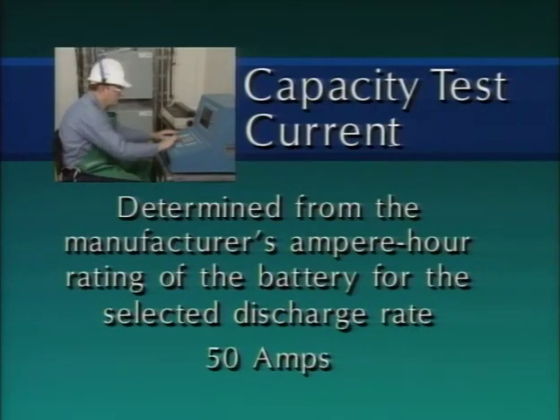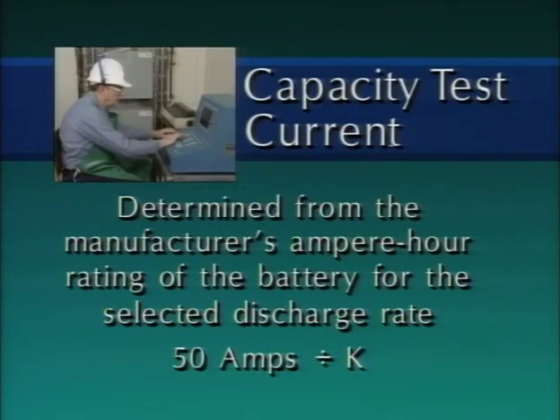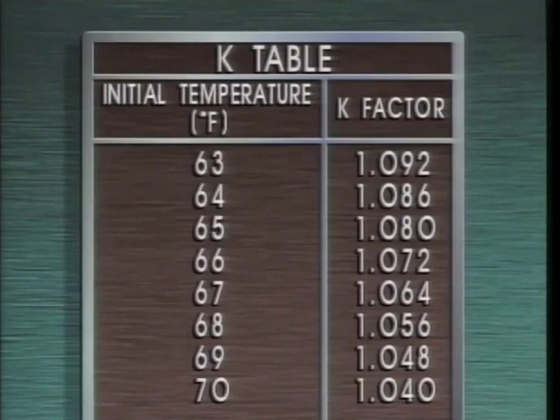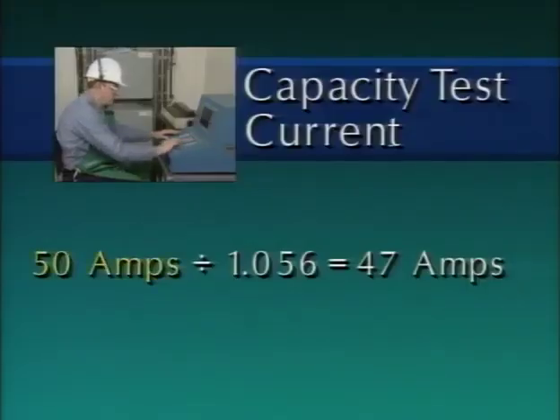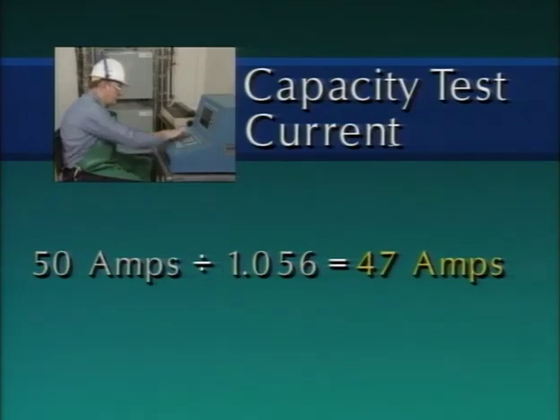The rated current, 50 amps in this example, is divided by K, which is a correction factor based on the average cell temperature. For example, using this temperature correction chart, if the average cell temperature is 68 degrees Fahrenheit, the correction factor is 1.056. The rated test current of 50 amps divided by the correction factor of 1.056 gives a test current of about 47 amps, which is entered into the control unit for the capacity test.